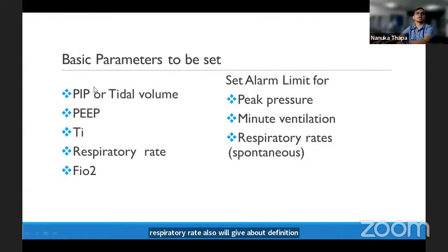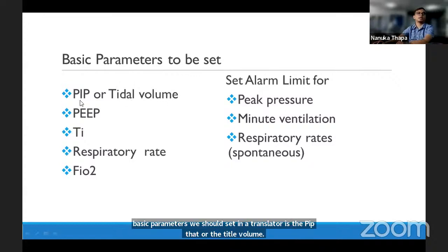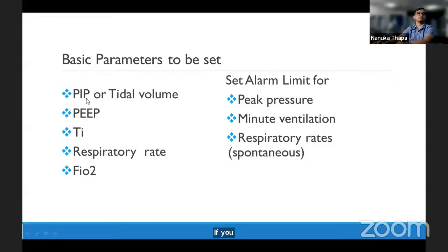The basic parameters we should set in a ventilator are the PIP or the tidal volume. If you use pressure control, then you set the PIP, the peak inspiratory pressure. For tidal volume, we'll see later how many ml per kg we should give, and what the tidal volume is for different illnesses and patients. The positive end expiratory pressure we usually set at 5, minimum 4 to 5 centimeters of water. The peak inspiratory pressure for a neonate begins at 10, and for an older adolescent we start with 15, 16. Tidal volume for neonates and children is around 8 to 10 ml per kg, or in a normal adolescent around 10 to 12 ml per kg.